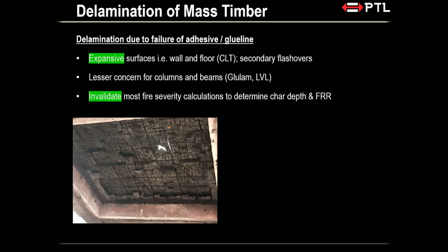Well, the delamination, for us fire engineers, we're more concerned when it is an expansive surface. So we're talking about floors or ceiling, right? So expansive surface where the delamination is a bit of an issue. We don't worry about the delamination of columns or beams because they have small surface area.